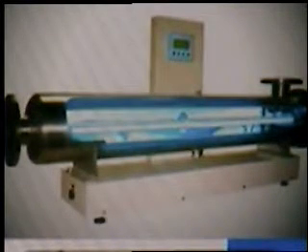Those are ultraviolet lights inside that reactor, and water flows past these ultraviolet light bulbs. What happens is any bugs that go by, as long as they get exposed long enough to that light, get a really bad sunburn, is the best way we can put it. It doesn't remove the bug, but it essentially makes it so that bug can no longer reproduce. It doesn't even kill it. It just makes it so that bug cannot reproduce.